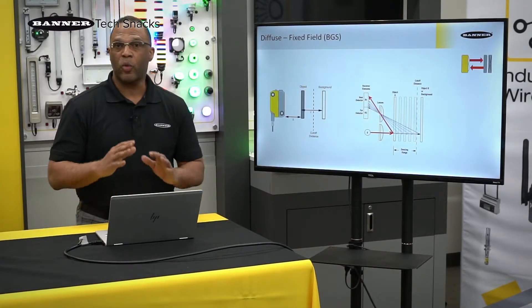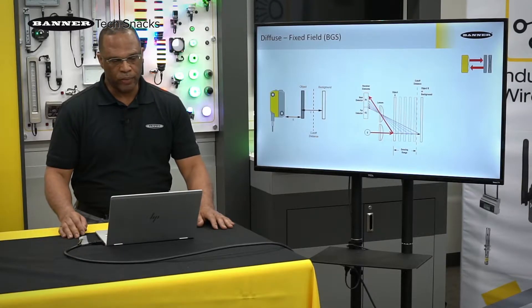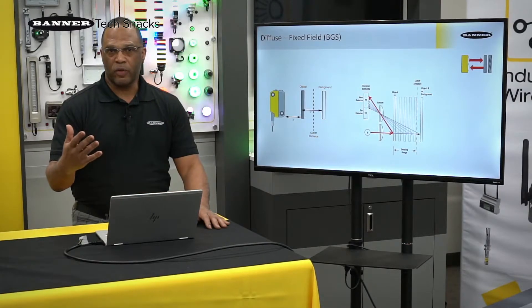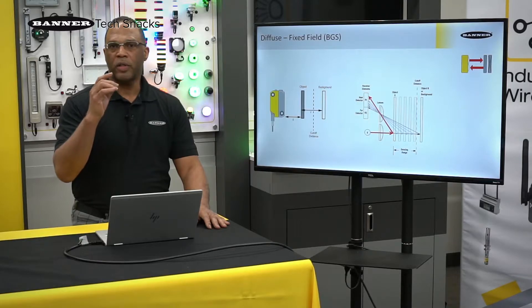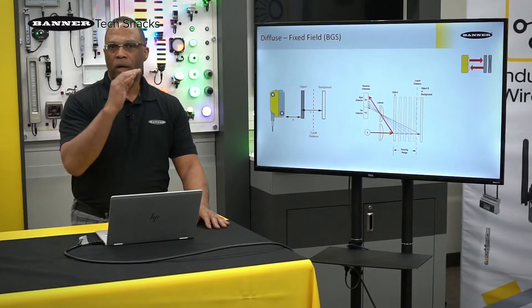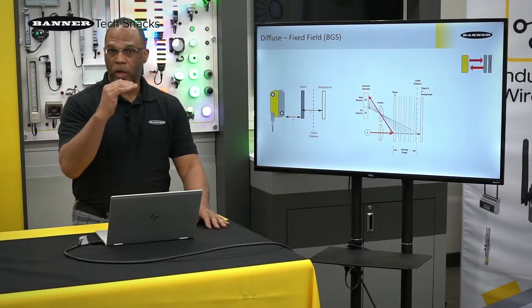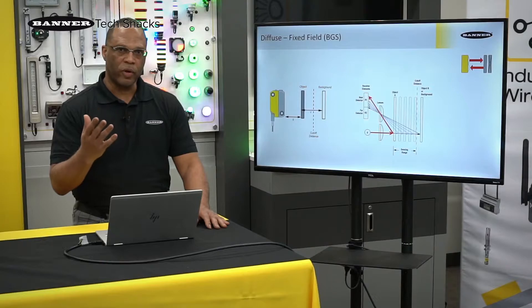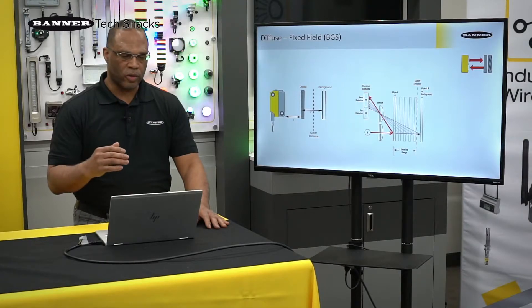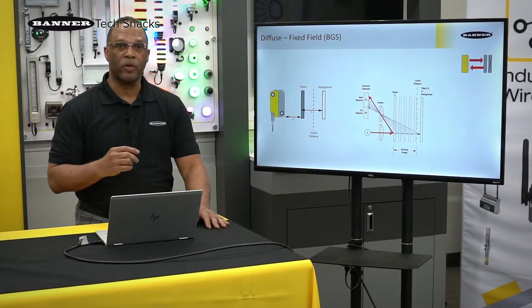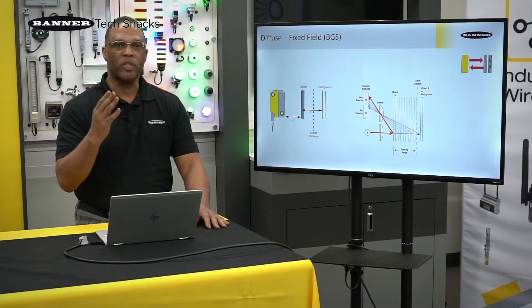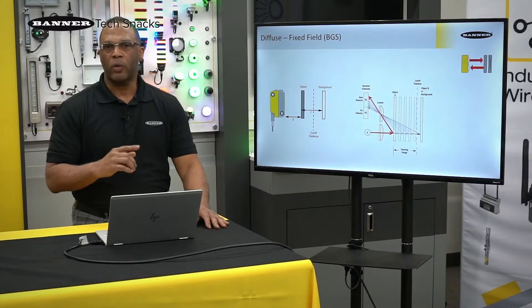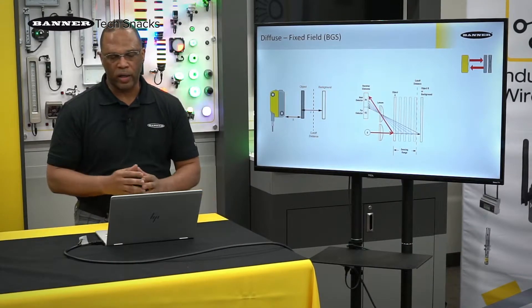Now, there is a way to get around this background issue. We have a variation of diffuse. Up until now, every sensor had one emitter and one receiver. What we've done with our fixed field sensors is we have one emitter and two receivers. That second receiver gives us cutoff because we are using it in triangulation.